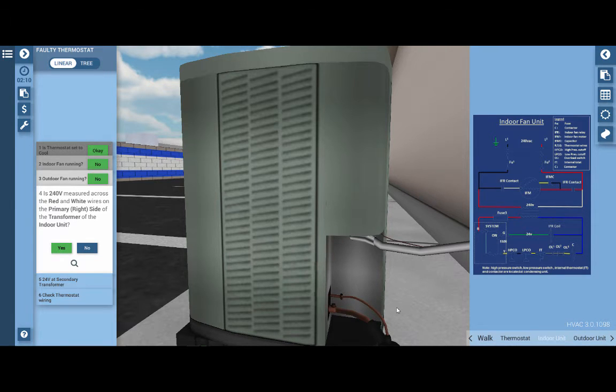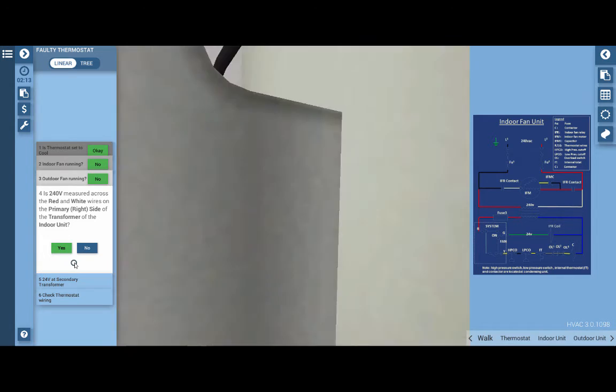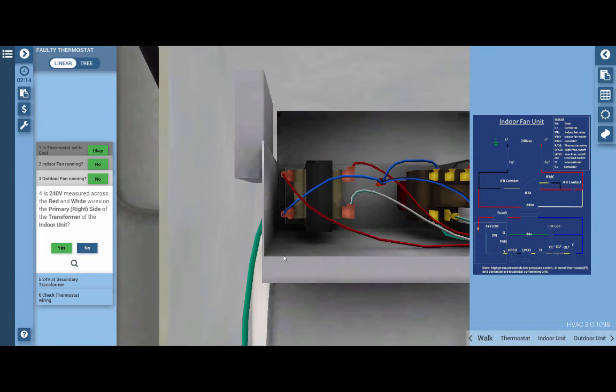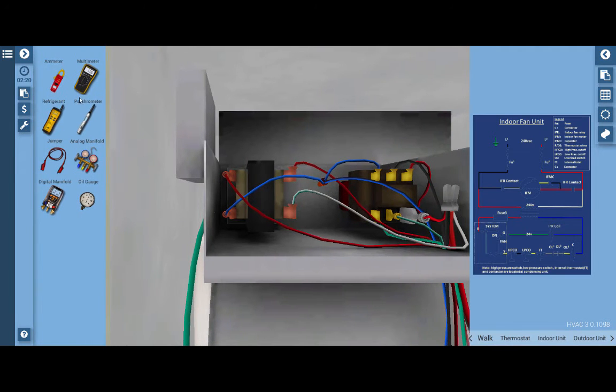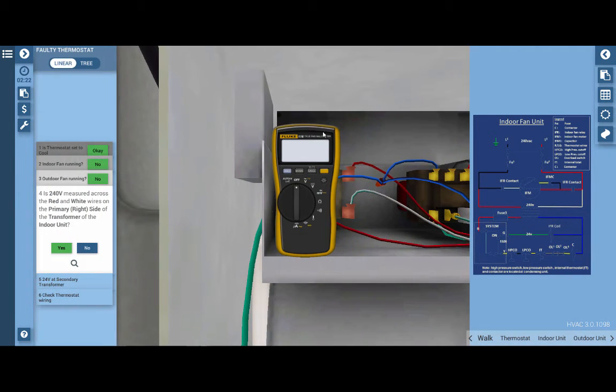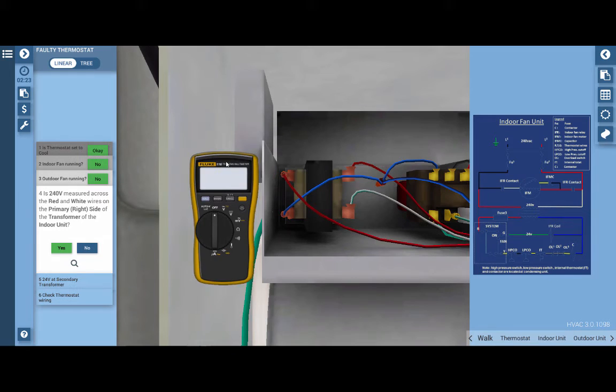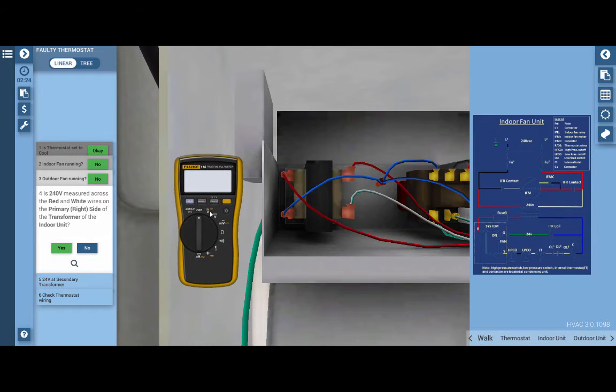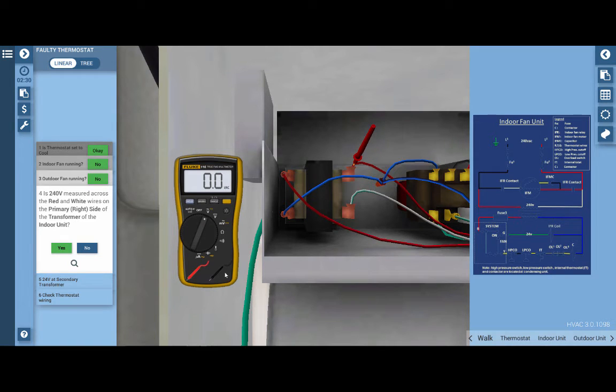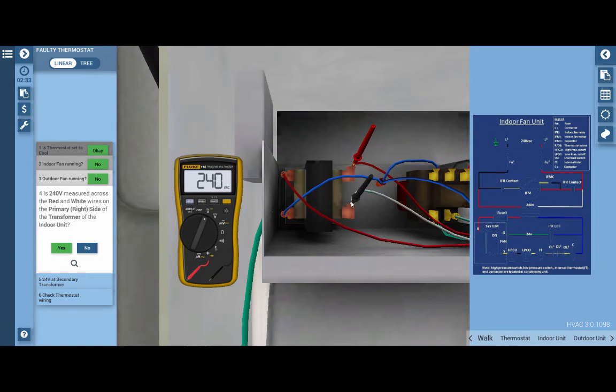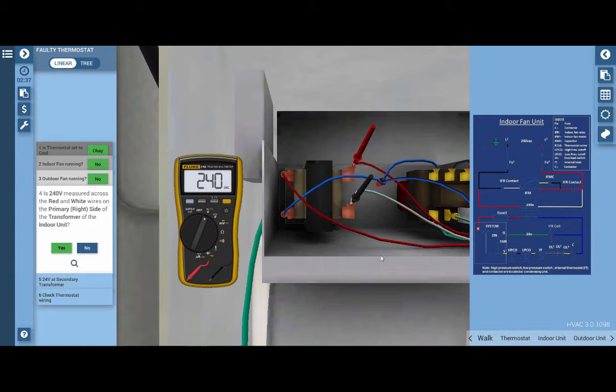This is going to be necessary to go back to the indoor unit. You can click on the indoor unit icon, or you can click on this little magnifying glass right here, and it'll take us right to the transformer connections. Click on the toolbox tab at the top left and remove the digital multimeter or voltmeter from the toolbox. Setting the selector dial to AC volts, we're going to place each of the leads at the primary connections of the transformer. And we should have 240 volts here, and as we can see, we do. So this verifies that we don't have an issue with a breaker or a disconnect at this point.